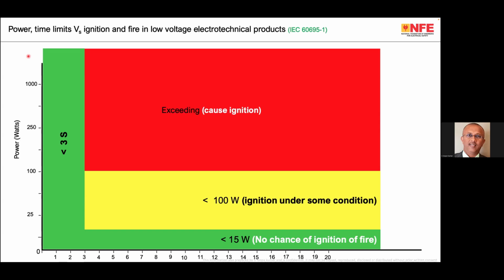So in a domestic or similar application, even if the heat produced is, let's say, 4,000 watts, but if the heat is reduced to less than 15 watts within 3 seconds, then there is no chance of fire. Within 5 seconds, if the heat produced is reduced to less than 100 watts, then you can see the yellow area. Ignition may happen depending upon the situation. So this concept gives you an idea. You can find this concept in 60695 part 1.